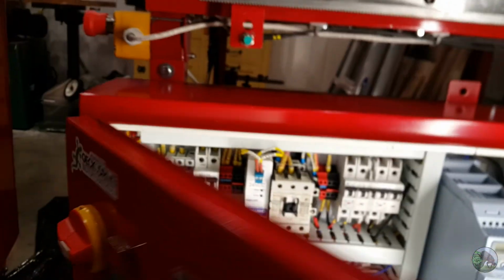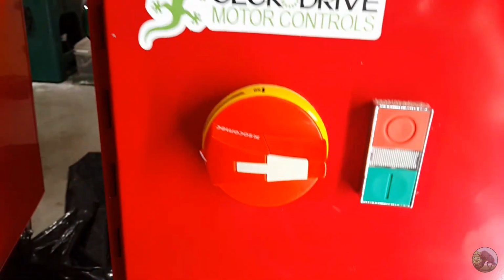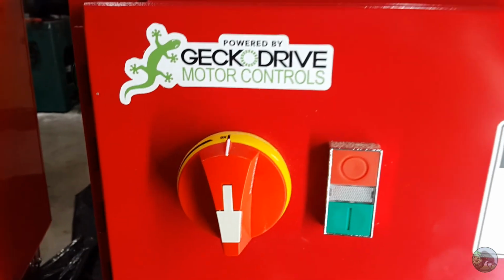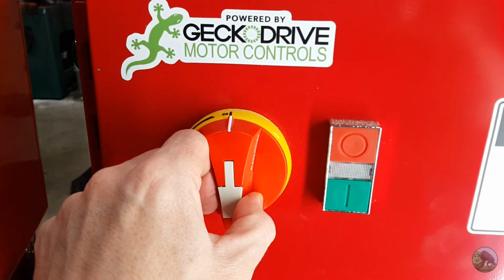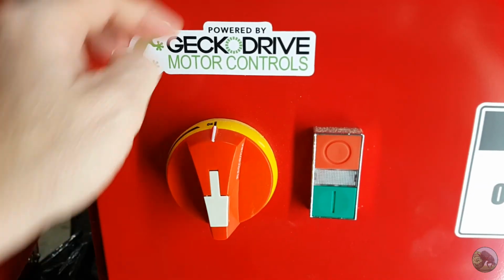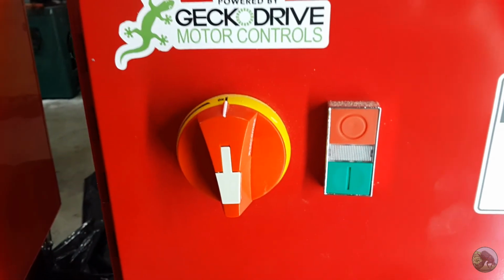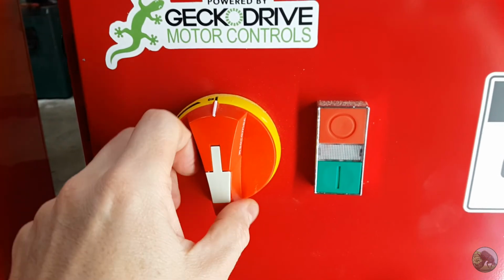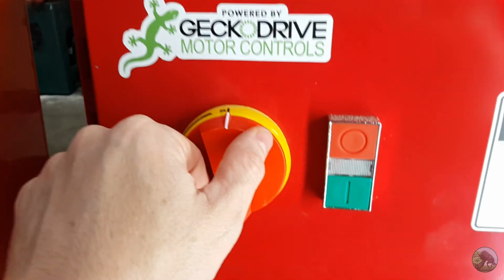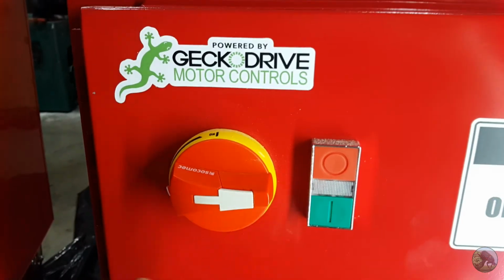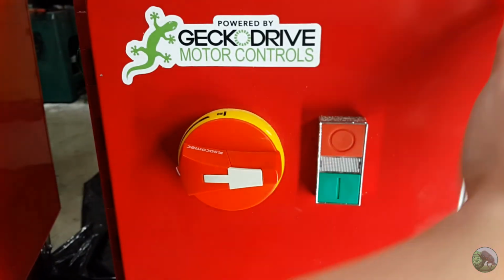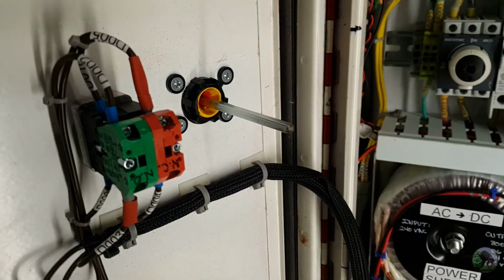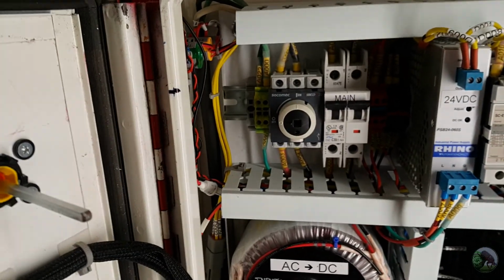So when you close the door, you're then able to turn on the power of the machine. And so when it's on, that locks in there, and if that bar is locked, then the door will not open. And so it's a safety feature for the electrician, so that they know that if the door is openable, then the power is off. And so I've configured my machine so that the bar can actually withdraw, and so that is not enforced.